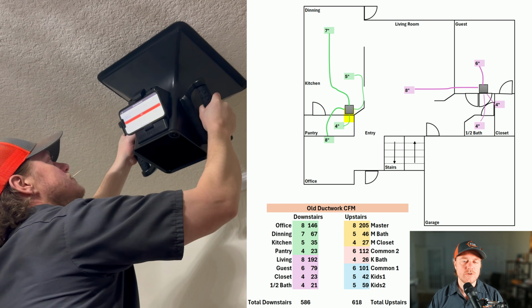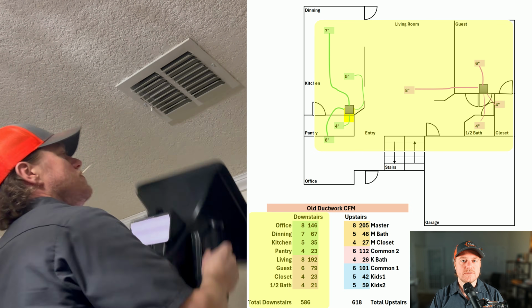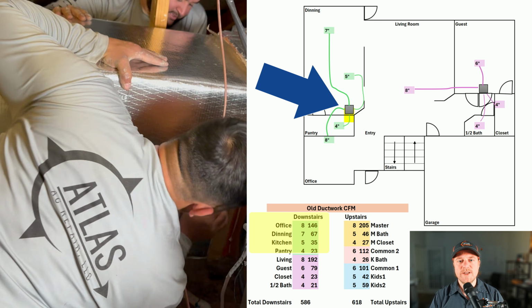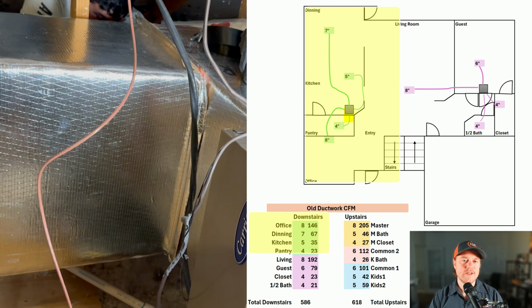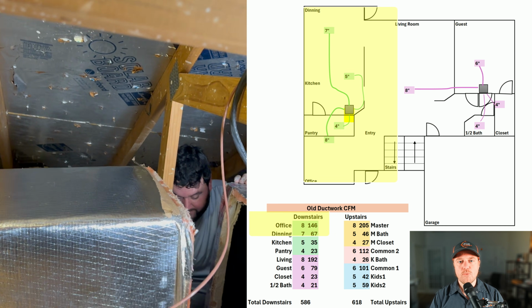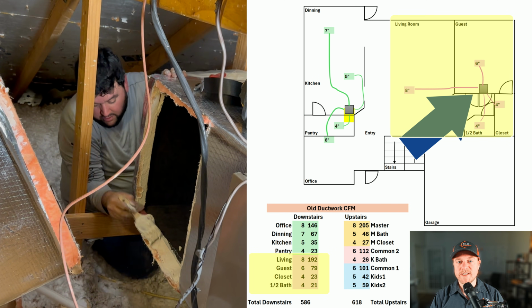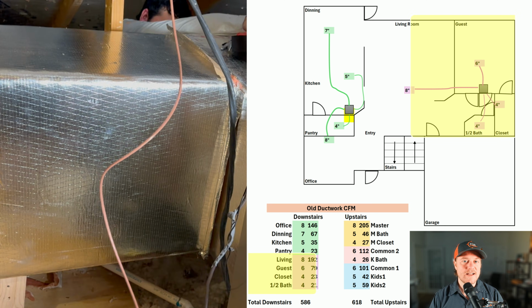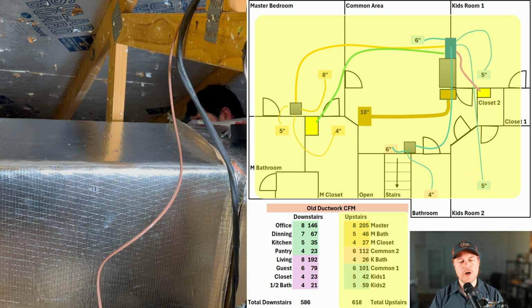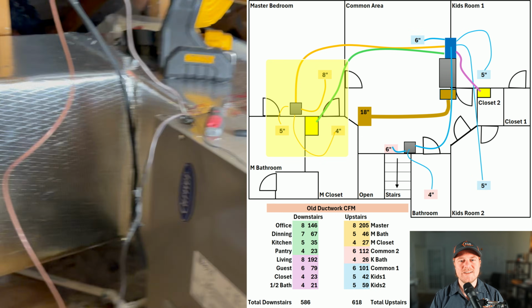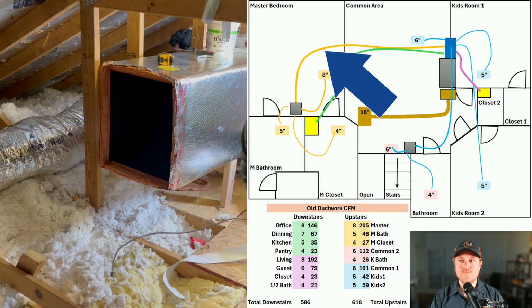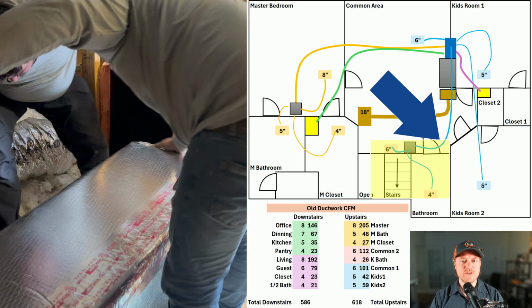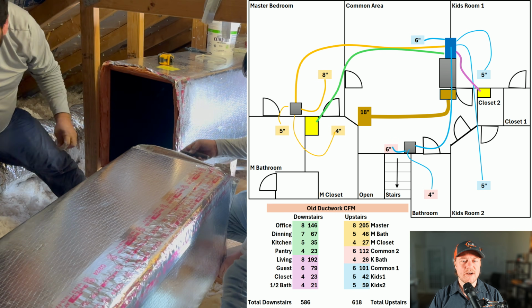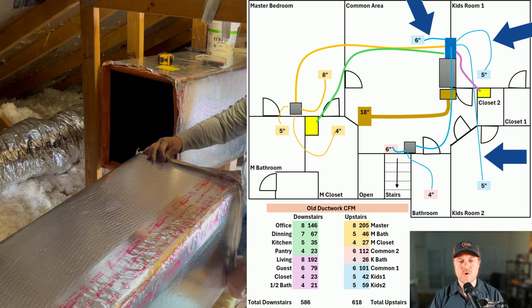Now to recap on the older ductwork, right here's the downstairs ducts, and in green we have one 10-inch feeding it, which is heating and cooling one half of the downstairs, and the grouping that I have in purple is also being fed by another 10-inch and is supplying the other half of the downstairs. And this section here is the upstairs ductwork. We have another 10-inch that is supplying the master bedrooms in yellow. We also have another 7-inch that's feeding these two ducts here, and the rest of the duct runs that are in blue are all connecting directly to the plenum.